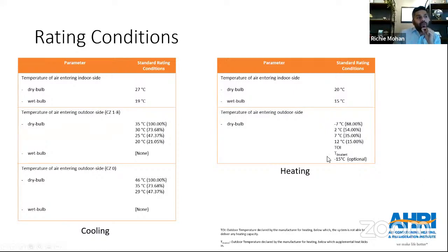There are some additional rating points which have been added for heating, one being TOL. This is the outdoor temperature, which is declared by the manufacturer, beyond which there cannot be any heating capacity that can be provided. So it's basically the ultimate bottom of the floor, and that needs to be certified and declared by the manufacturer. Beyond that, we also have the T bivalent. It's basically the temperature condition for heating beyond which the system will require supplemental heating. That needs to be given as part of the declaration by the manufacturer when complying with the standard.